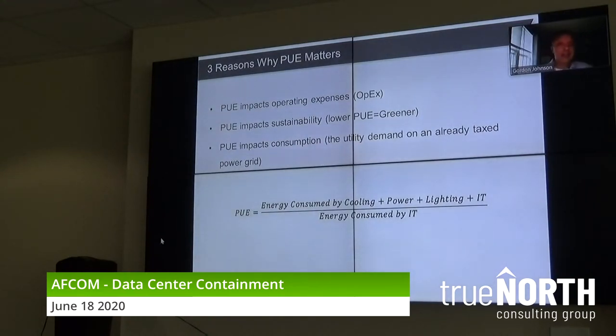So an energy-efficient data center, a perfect data center, would have a PUE of 1, meaning if the IT heat load is, say, 1 megawatt, then the energy consumed is 1 megawatt, and the numerator is 1 megawatt. You'd have no lighting, you'd have no UPSs. You'd have free cooling going on all year. The reality is most people don't see anything even close to that. But again, the goal is to get as close to 1.0 as possible when it comes to a PUE.